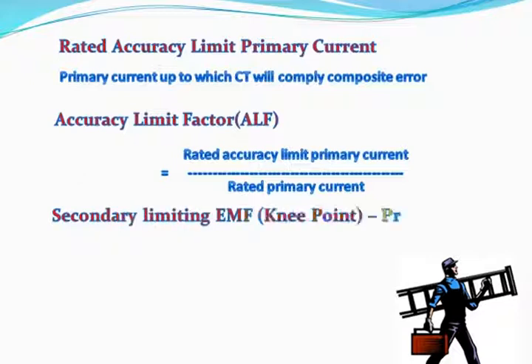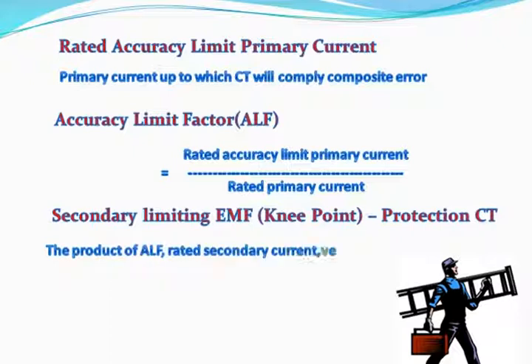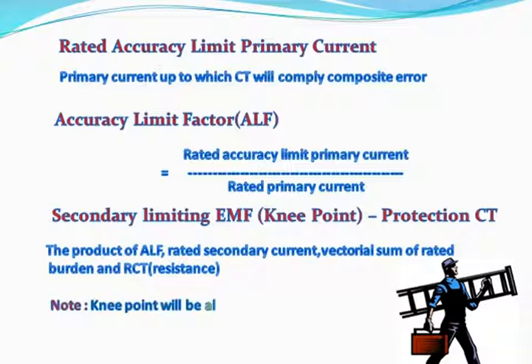The secondary limiting EMF, or knee point, for protection CT is the product of ALF, rated secondary current, and the vectorial sum of rated burden and RCT. Please note that the knee point will always be higher than this calculated value for protection CT.